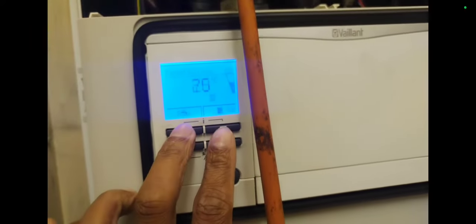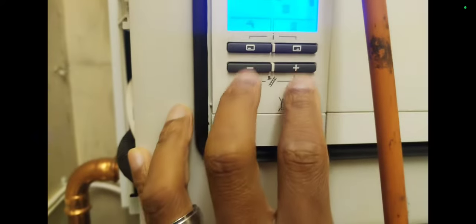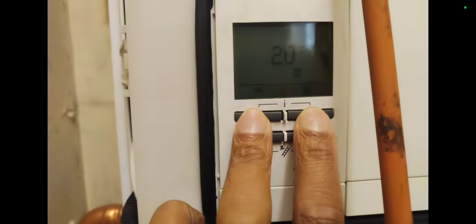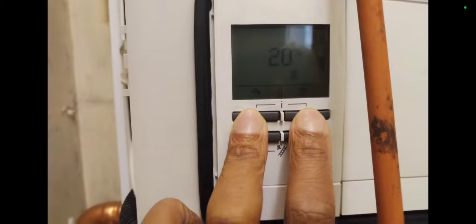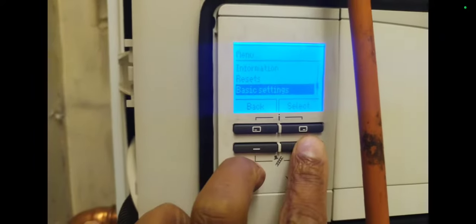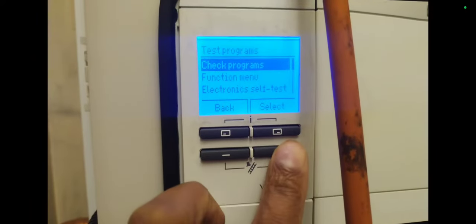So here we go, target flow temperature 75. So now the boiler shouldn't lock out too early. Okay, pumps running. Gonna get the boiler back into service mode again. Installer level 17. Okay, test programs, check programs. Then we want P1, select, and then we have our boiler in high fire.